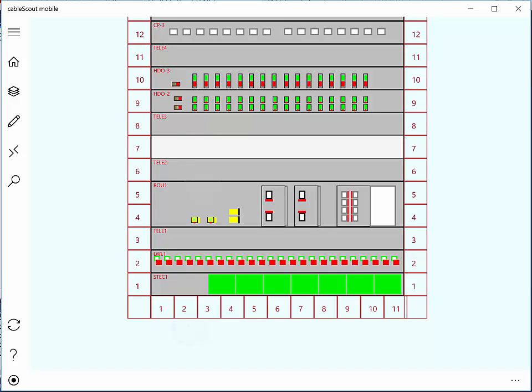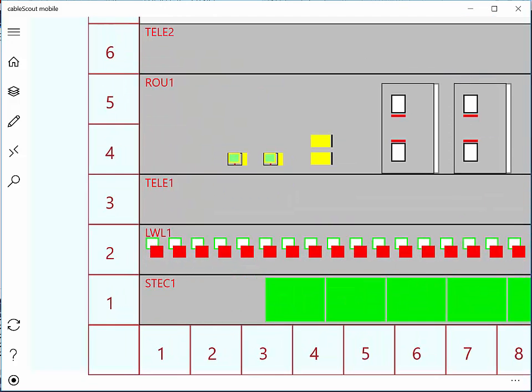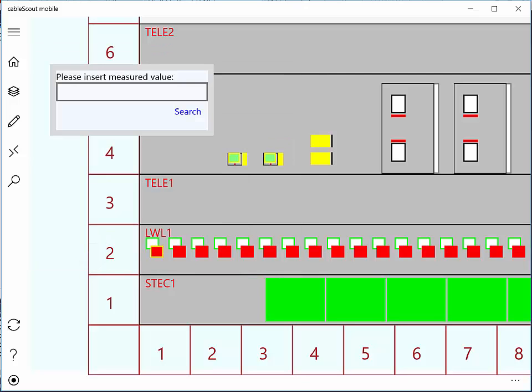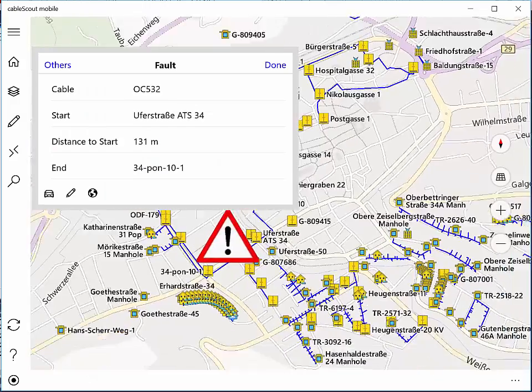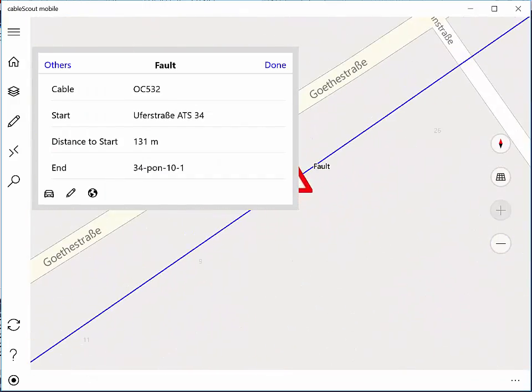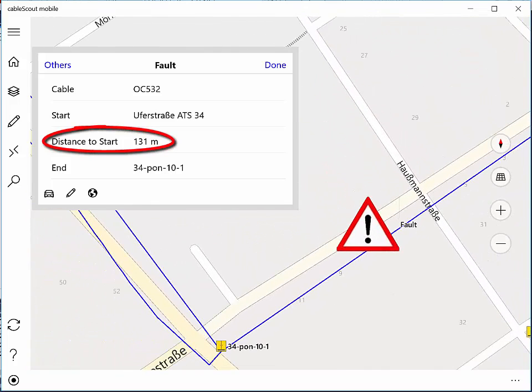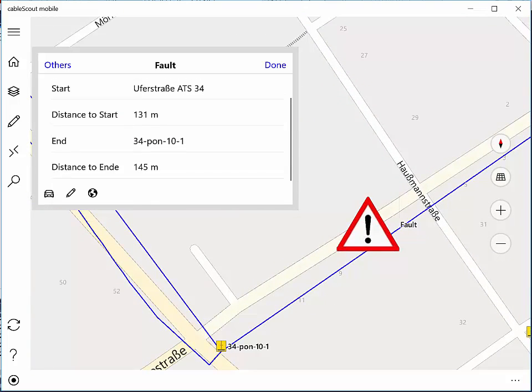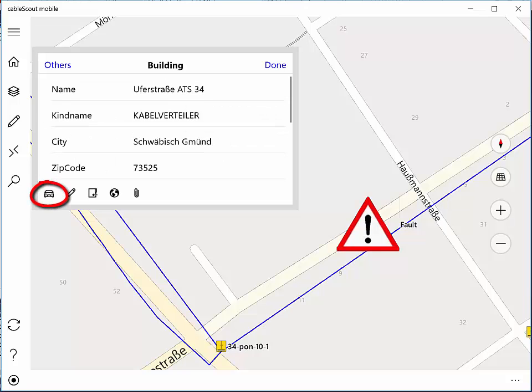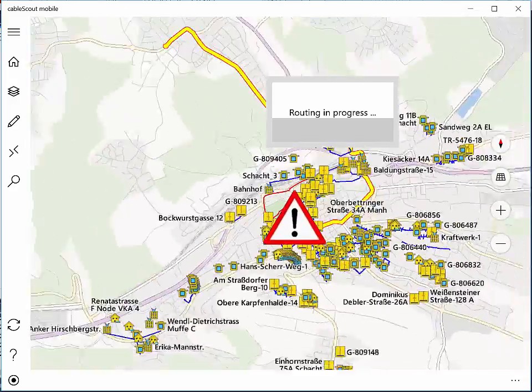The last part of this demo, fault traces, is shown on a Windows tablet. From an internal view of a rack, a user can select a port and insert an OTDR value. This starts a network traced from the port and the location of any detected faults will be displayed. Additionally, the distance between the port and faults will be calculated and a user may choose to activate the car navigation functionality within CableScout Mobile and be immediately directed to the fault location.